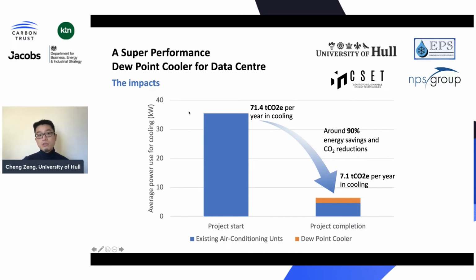Once we turned our dew point cooler on, the existing cooler dropped off. Energy consumption dropped from 35 kilowatts to less than 10. Our dew point cooler only consumes about 2 kilowatts, and the rest of the blue area is the existing air conditioning running on standby.